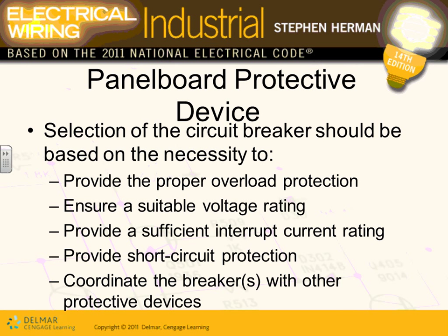And when you coordinate, remember the curves that you were playing with last quarter. Coordinating them means, if I have a short circuit in that fixture above your head, do I want the switchgear down in the basement of Dunwoody to trip? Of course not. So you coordinate the overcurrent protection devices for selectivity, so the circuit breaker closer to the ground fault or the short circuit will trip first. Any comments, guys, about selecting the circuit breakers?